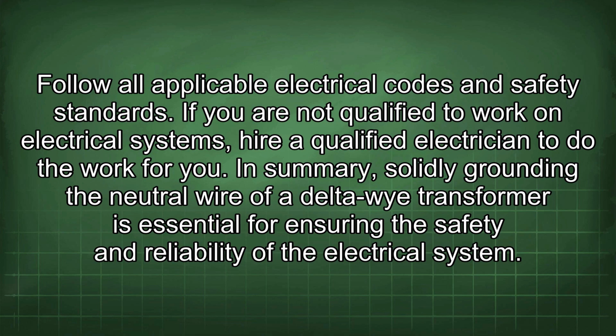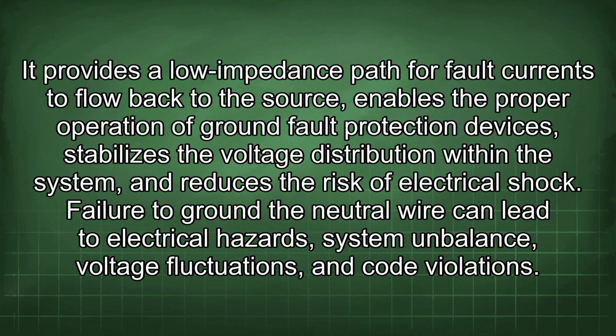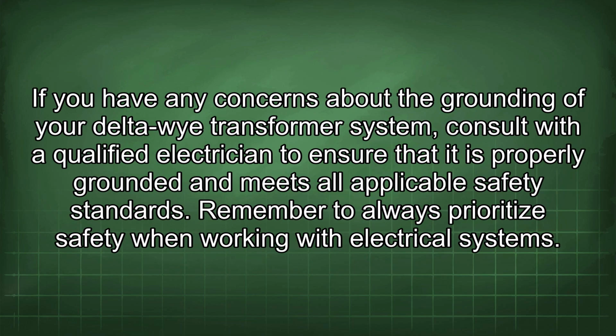In summary, solidly grounding the neutral wire of a delta-wye transformer is essential for ensuring the safety and reliability of the electrical system. It provides a low impedance path for fault currents to flow back to the source, enables the proper operation of ground fault protection devices, stabilizes the voltage distribution within the system, and reduces the risk of electrical shock. Failure to ground the neutral wire can lead to electrical hazards, system imbalance, voltage fluctuations, and code violations. If you have any concerns about the grounding of your delta-wye transformer system, consult with a qualified electrician to ensure that it is properly grounded and meets all applicable safety standards.